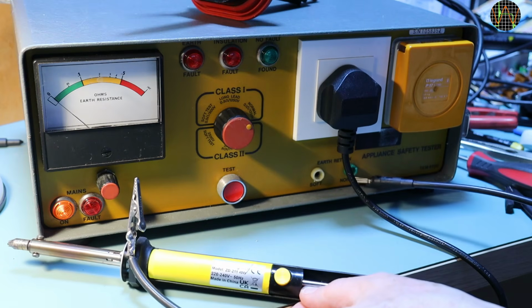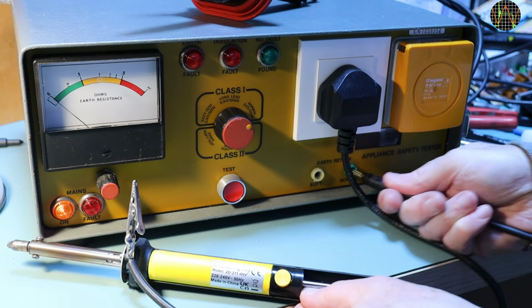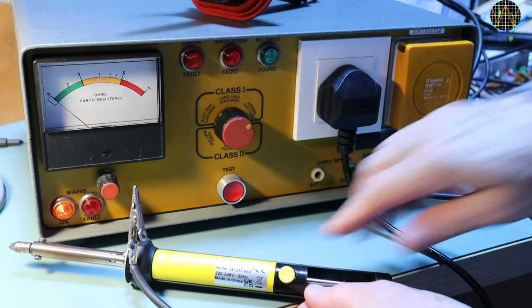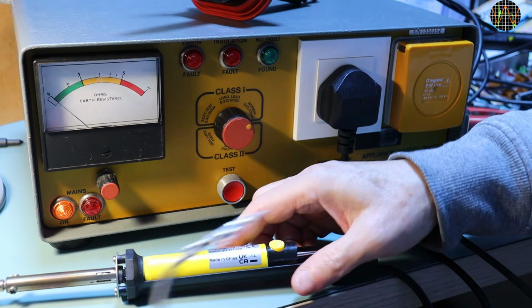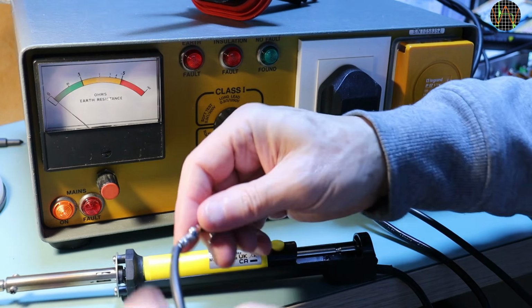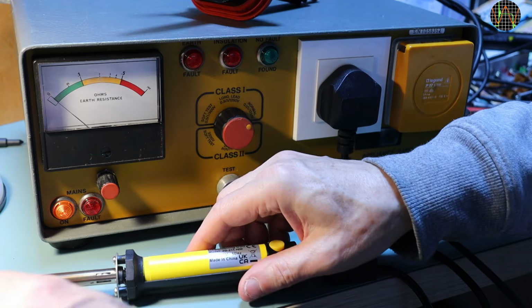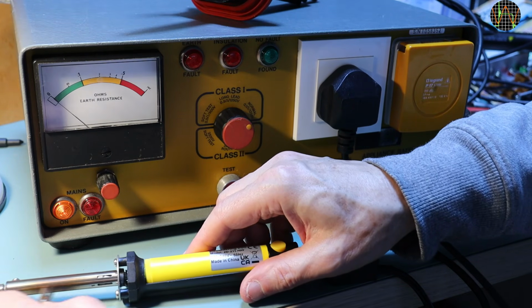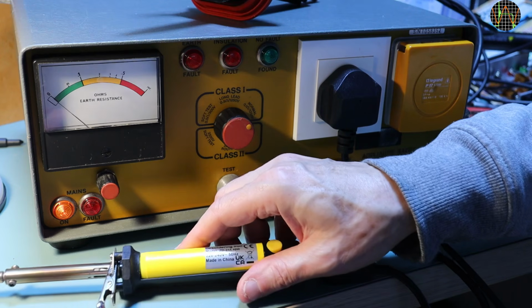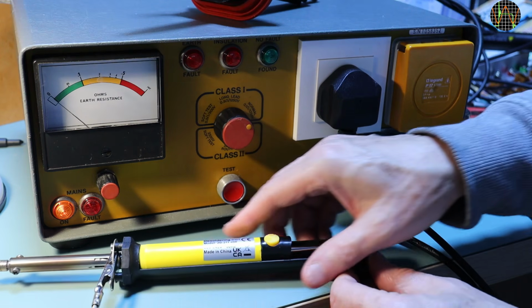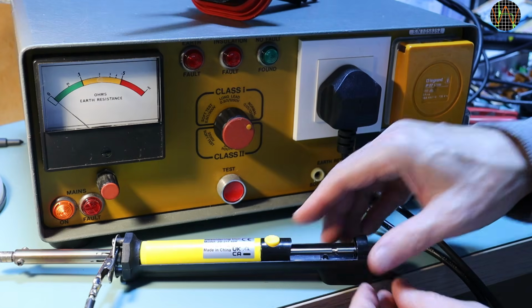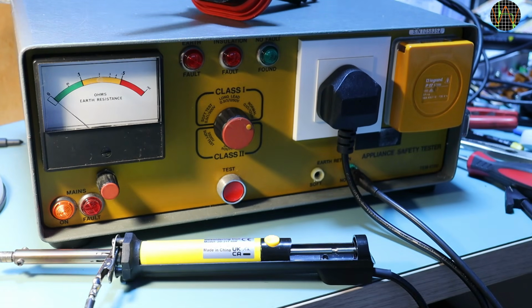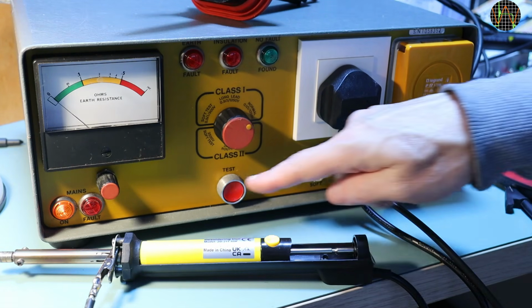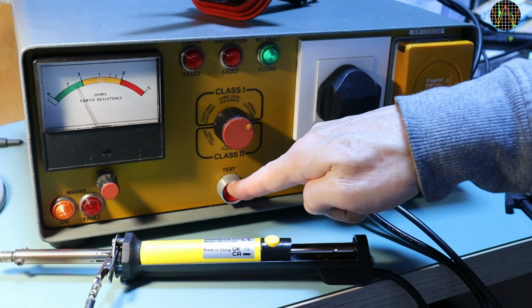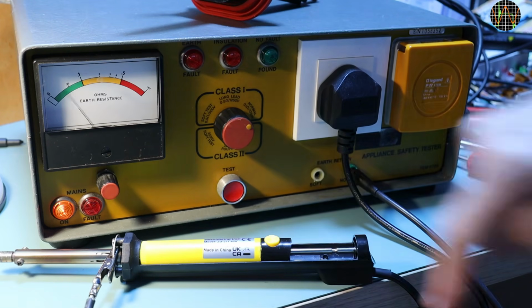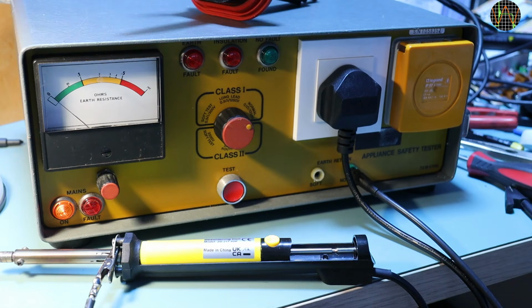I have this desoldering pump with an integrated soldering iron. It works reasonably well, and with all items coming from the Far East, I had already verified that the earth was properly connected. But now I can do a much better test, including insulation at 1250 volts. I think the iron will survive, and if not, it's not really an expensive thing. Here we go. Slightly below 0.1 ohm, and it passes both tests.